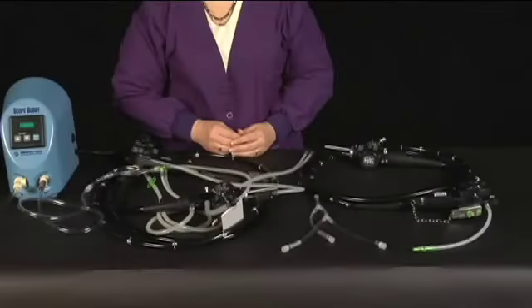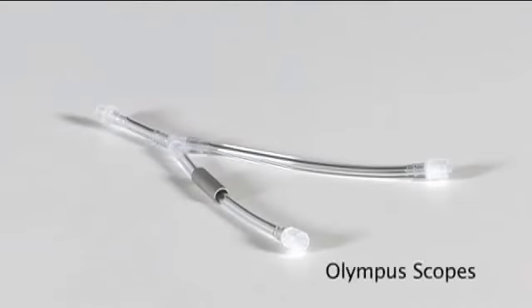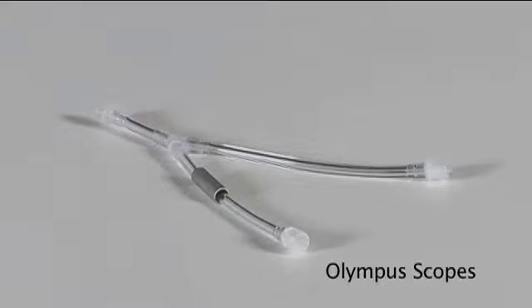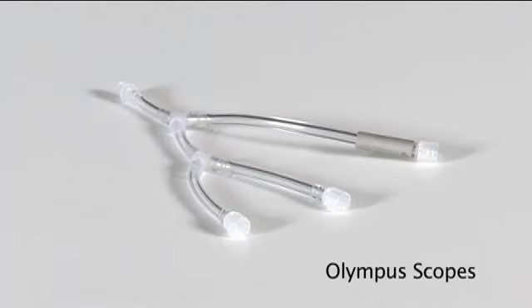Examples of how to select the appropriate Scope Buddy universal cleaning adapter will be demonstrated. For Olympus scopes. For Olympus gastroscopes, you would select the universal cleaning 2-way adapter, which would attach to the scope's channel irrigation tube. For Olympus colonoscopes with an auxiliary water channel, you would choose the universal cleaning 3-way adapter. Two ends of the 3-way adapter would attach to the scope's channel irrigation tube, and the third end would attach to the auxiliary water channel's flushing tube.